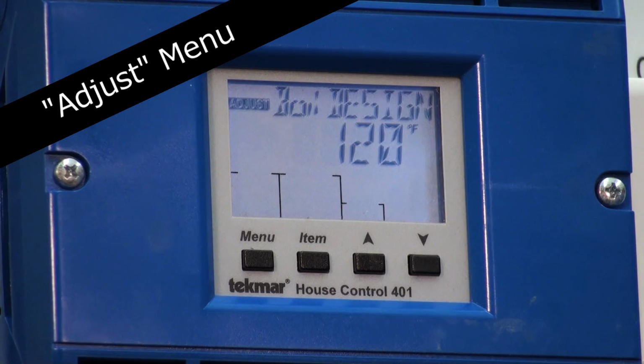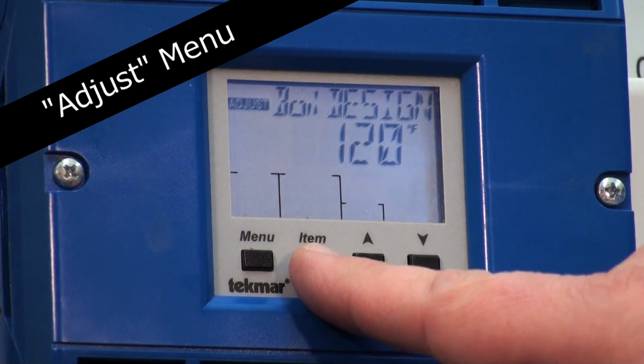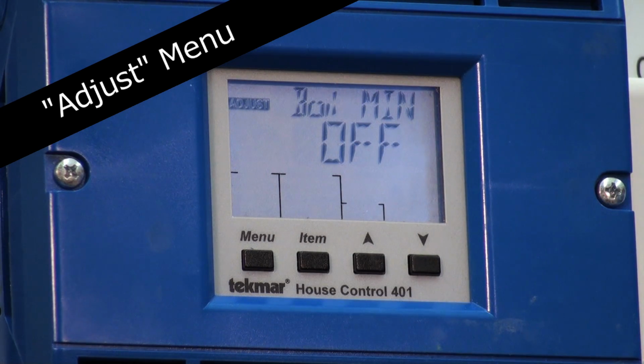Boiler design. This is the water temperature at what we are going to be at the -15 if that's your design point outside. So -15, we're targeting 120. That's your setting here. The boiler minimum, in this case being a ModCon boiler, it is off. We don't care about the return water temperature, the colder the better. Cast iron boiler, you might set that to a minimum of 140 to protect the boiler.